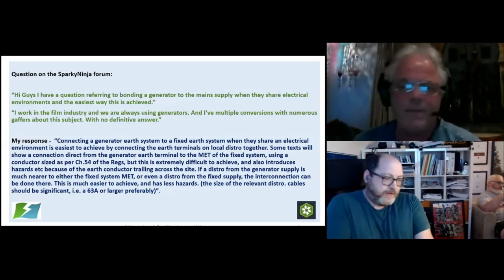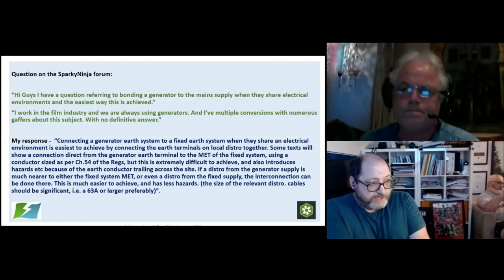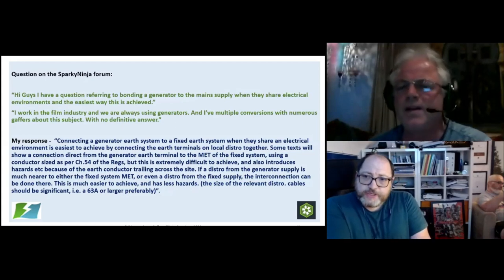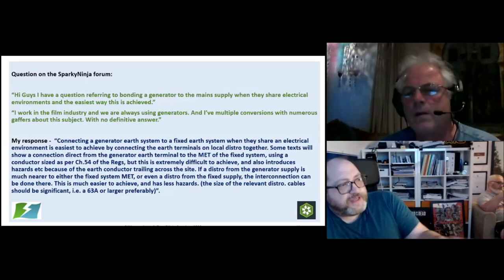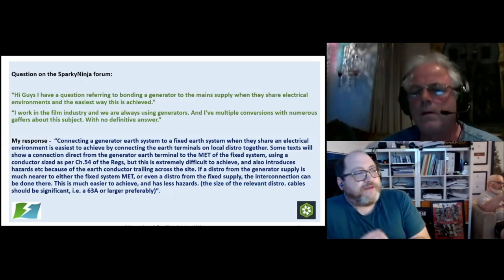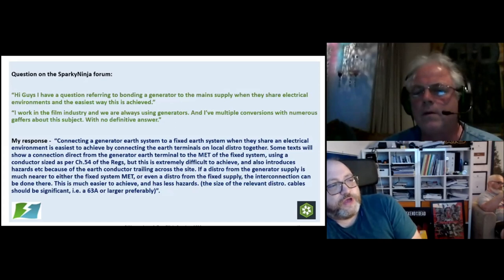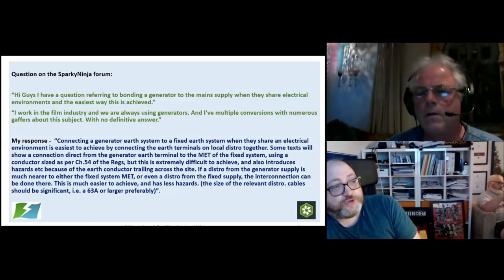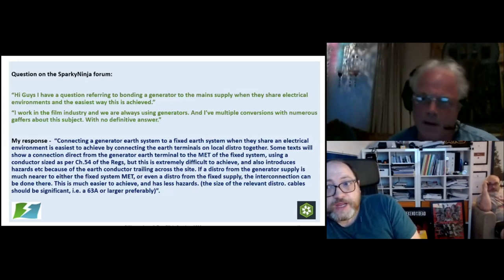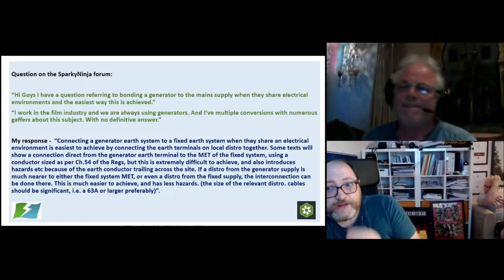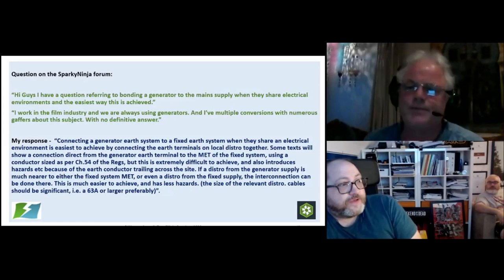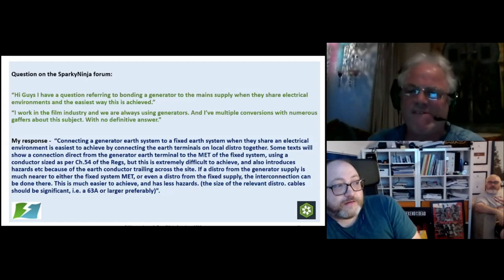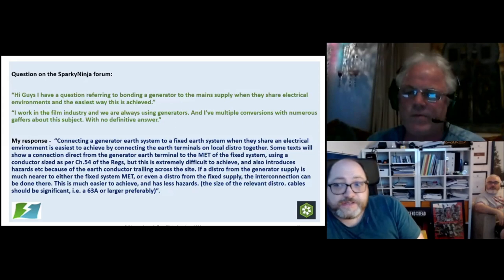Now, I was just thinking about, and Paul's mentioned this in chat actually, I'll read Paul's response. He says, I get this answer. My concern would be if the building supply failed, an earth fault on the temporary system could potentially backfeed into the public supply if the fault path has a lower impedance, and could possibly cause a hazard for the short period of the fault. If the impedance path is of lower impedance for the fault path back through structural steelwork or similar, could that be considered an acceptable option, because that's conductors under 7671?